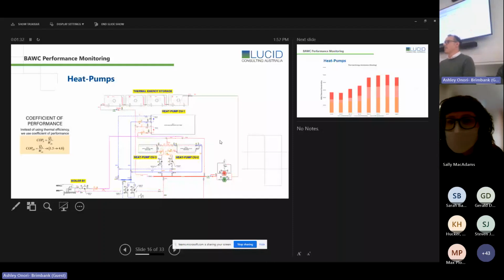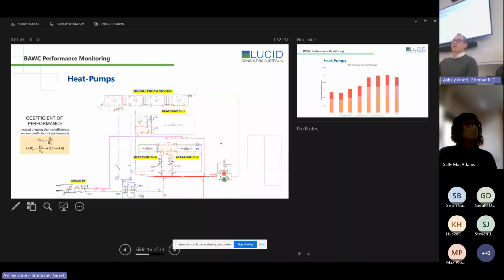Traditional thermal systems within buildings are operating with flow and return temperatures of 80 degrees and 60 degrees return. That's very high. For the vast majority of heat pumps, you're not achieving that level of heat, so you're not achieving the 80 degree temperature efficiently. So to achieve the optimized performance of a heat pump, to maximize the energy efficiency, this facility actually runs a very low heating hot water temperature. From memory, it's 53 degrees, which is a lot less than the 80 degrees.